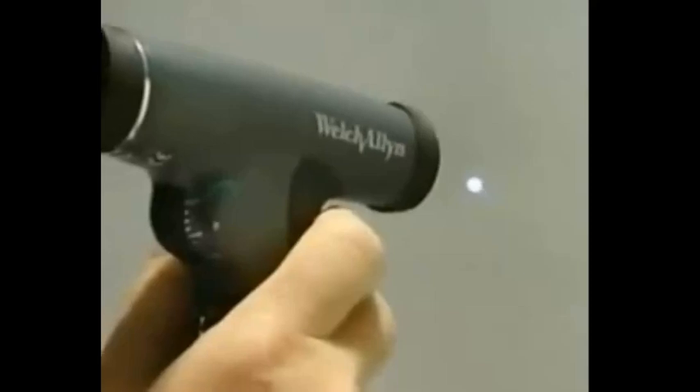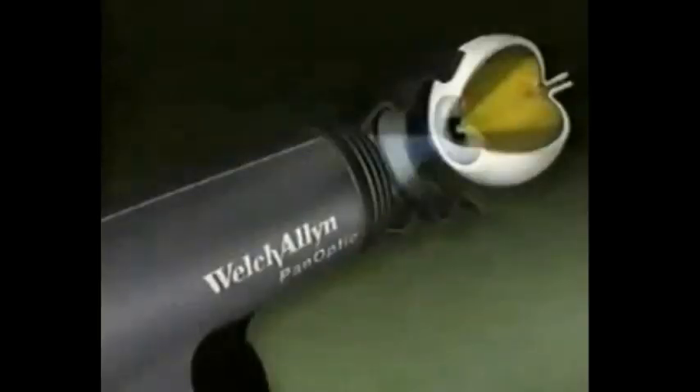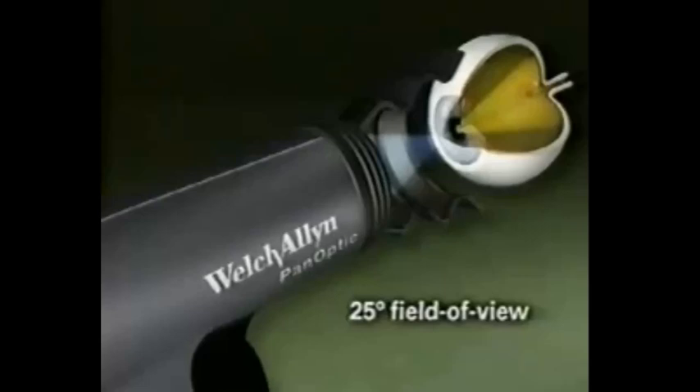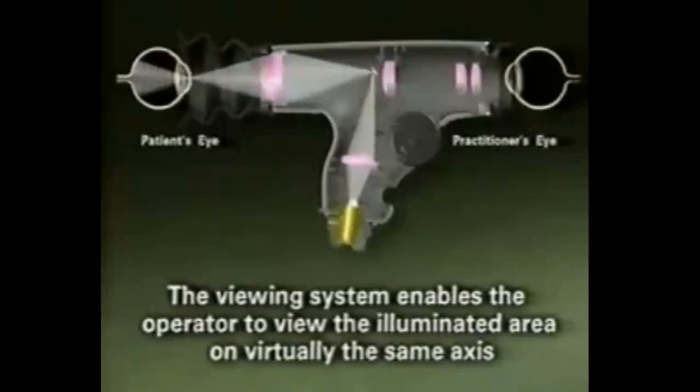Welch Allyn's patented new axial point source technology converges the bright white halogen HPX illumination to a point at the cornea, allowing easy entry into even the smallest pupils. Then, axial point source optics enables the illumination pathway to diverge to the retina, creating a very wide illuminated area of the fundus. Simultaneously, the scope's unique viewing system allows the operator to view the illuminated area on virtually the same axis, creating the widest field of view attainable in undilated ophthalmoscopy.